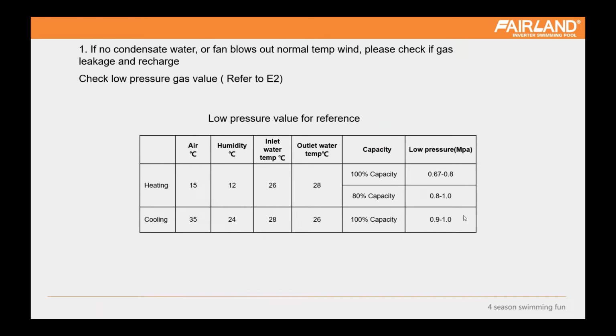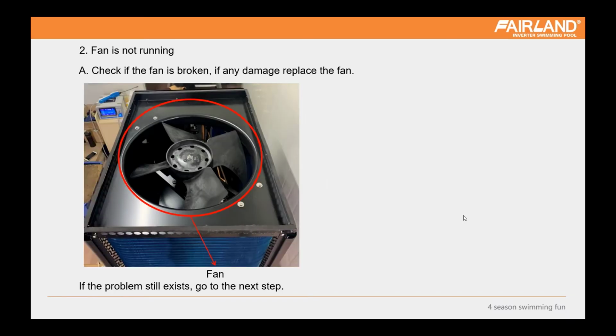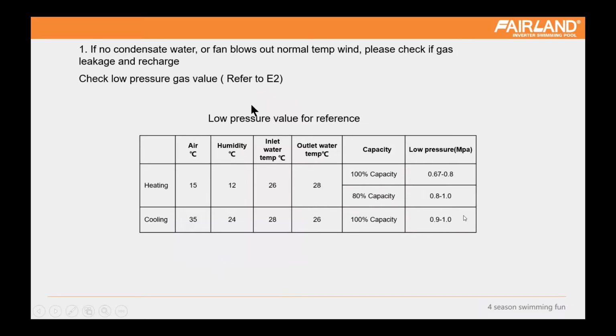And if there is no condensed water and no cold wind, maybe there is a lack of gas. We need to check the low pressure value for reference. And sometimes you don't need to check that: if there is no condensed water and no cold wind, maybe you can also check the running percentage of the compressor. If the running percentage is not normal, it's maybe just 60%, and at that moment it is heating the pool up to the desired temperature.